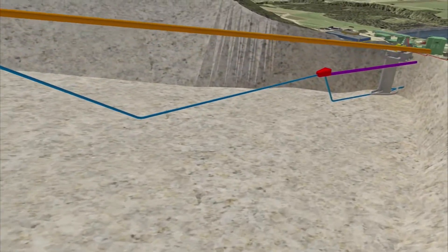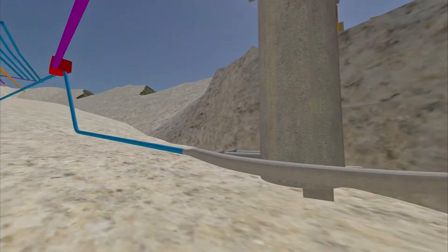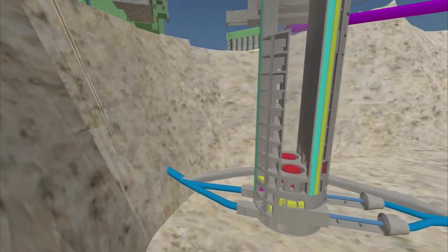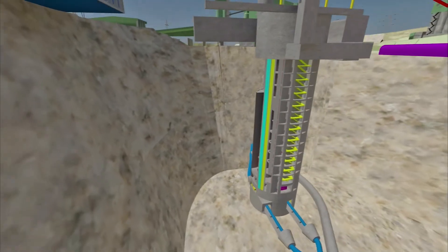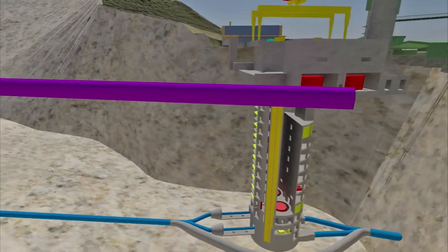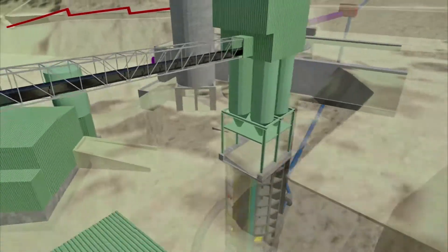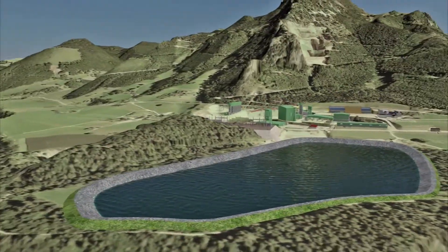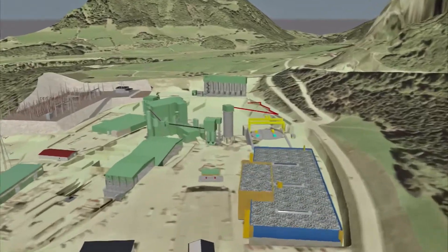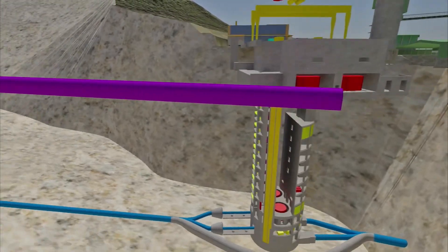The overall efficiency of this system is approximately 80%. Using full-size converters guarantees a completely flexible plant concept, so that power generation output can be seamlessly adapted to compensate for variations in demand. The turbines and generators are installed inside the 100-meter-deep power station shaft. All that can be seen on the surface is the lower water reservoir in an existing gravel pit, the open-air switchgear and the top of the power station shaft. All the other plant components are underground.